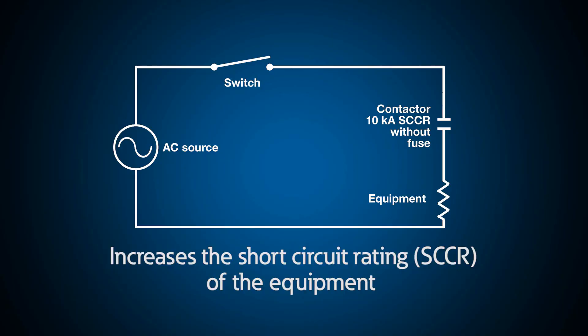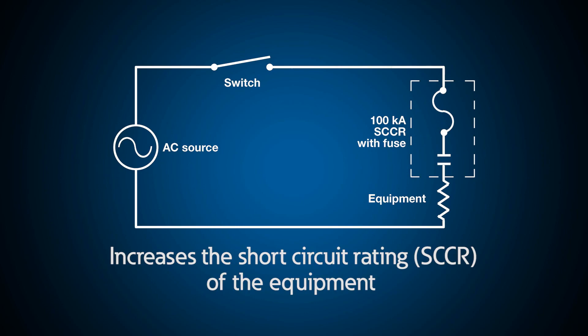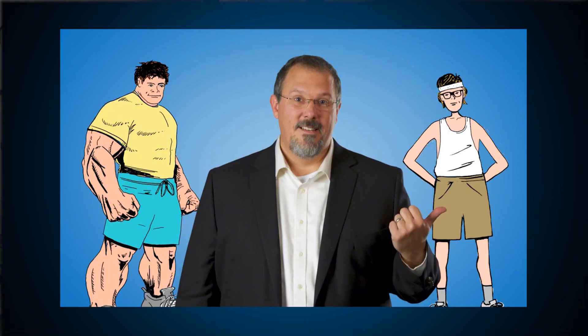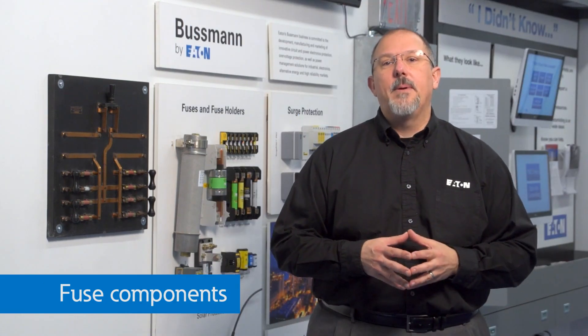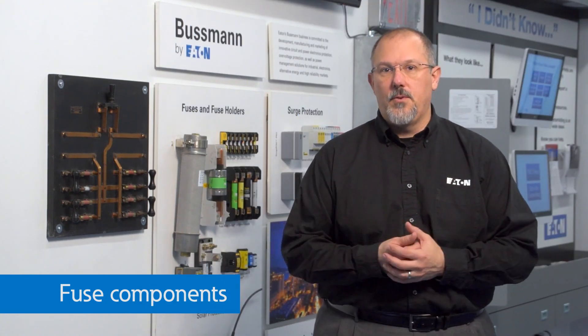When fuses are used ahead of equipment, they are often applied to increase the short circuit current rating (SCCR) of that equipment. This fundamental principle was discussed previously using a weight-lifter example. Let's now look at the components that make up a typical fuse.